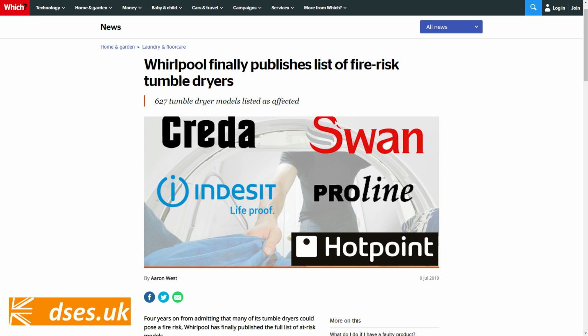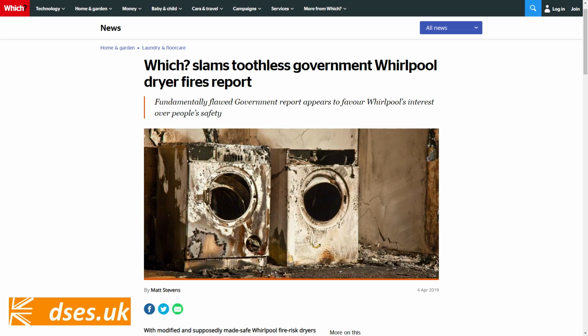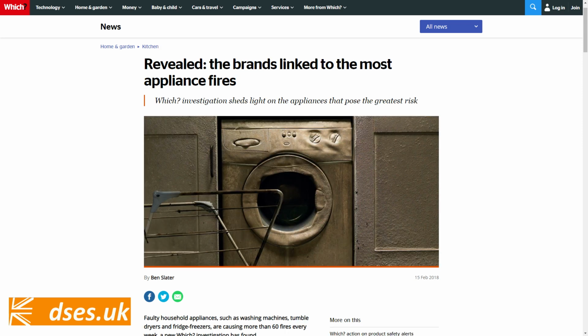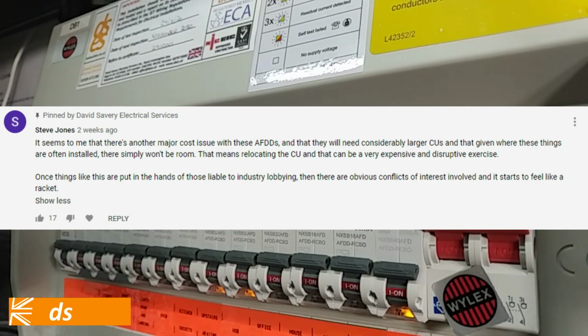Those would all be classed as electrical fires, as they started in a running appliance. But the problem there is apparently down to fluff getting onto the heating elements, which has nothing to do with your distribution electrics, and won't concern your AFDD or anything else. At least, not before the fire starts, spreads, and then melts the bloody cabling. Steve Jones says, it seems to me that there's another major cost issue with these AFDDs, and that they will need considerably larger CUs, and that given where these things are often installed, there simply won't be room.